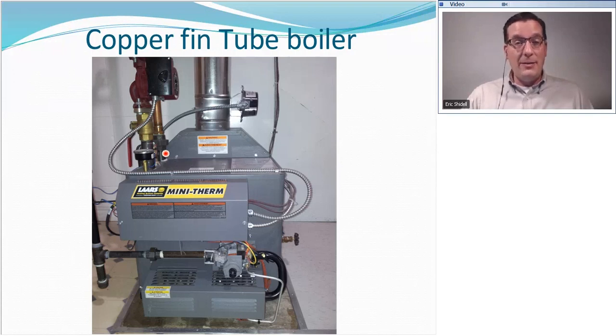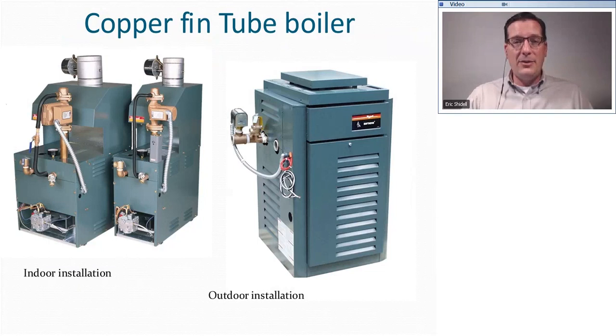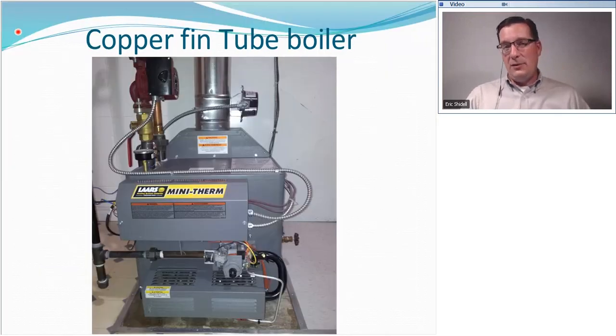But by the time you get there, that label may be gone or corroded or burned off by a torch, or who knows what happened to it. Different brands are going to have different nomenclature, and it's a little more difficult to identify which direction the water moves because they're in the same plane. So one convenient thing that you can look for in those applications is, where is the boiler measuring its temperature? Where is it sensing temperature?